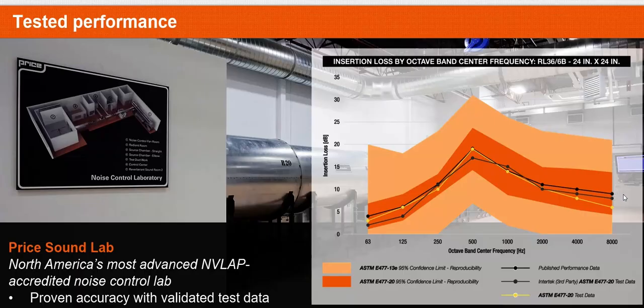And in the past, reproducibility, meaning trying to reproduce the same results in different labs, had a difference in performance. So the standard and the body of the standard used to believe the information they were presented with, to the point that for the same silencer with the same materials, and even though the way sound travels inside ductwork hasn't changed for almost 100 years, it has never changed since it was quantified and discovered, it should not have that crazy of a gap. So all of a sudden, for 2 silencers of the same geometry, same free area, manufacturer A could give you up to 16 decibels of performance higher than manufacturer B and C.